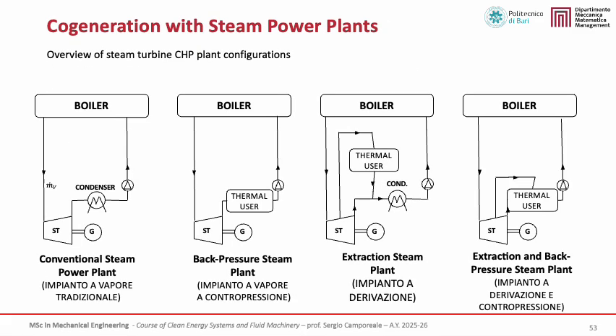Here we can see the main configurations of steam power plants used for cogeneration. Starting from the left, we can see the conventional steam power plant without cogeneration. In this case, all the steam expands to the condenser and no useful heat is recovered. The second configuration is the back pressure steam plant, where all the exhaust steam exiting from the turbine is directly supplied to the thermal user, ensuring full heat recovery but limited flexibility.